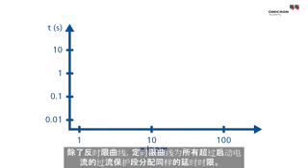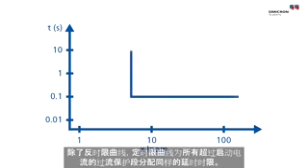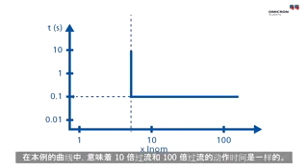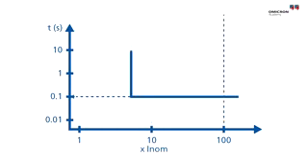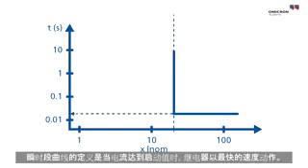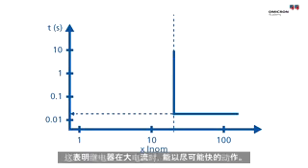Other than inverse time curves, definite time curves assign the same delay time to all of the overcurrents that exceed the pickup value. In our curve example, that means that the trip time is the same for a 10-fold overcurrent and a 100-fold overcurrent. The definition of an instantaneous curve is when a relay is operating at its maximum tripping speed after the pickup current has been exceeded. That means that the relay trips as fast as it can for very high currents.